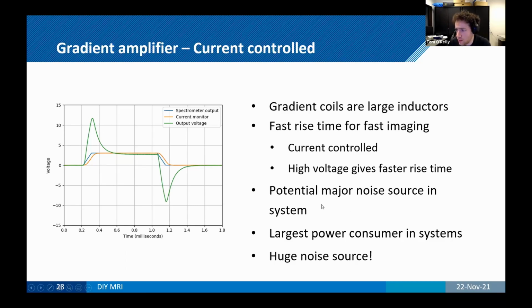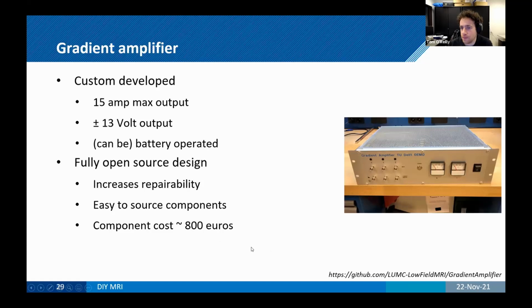For us, the gradient system was by far the most noisy part of the system. So if we didn't properly take care of the noise, our noise went up about 400-fold when we switched on our gradient amplifier. It's also by far the largest power consumer in the system. So it's a huge noise source electronically. The gradients themselves on low field are essentially silent because your Lorentz forces are so small on the gradient coils because your field is lower, so much quieter. For the gradient amplifier, we just developed it ourselves because one of the things with low field is that there's not a lot of vendors who will supply stuff for low field.